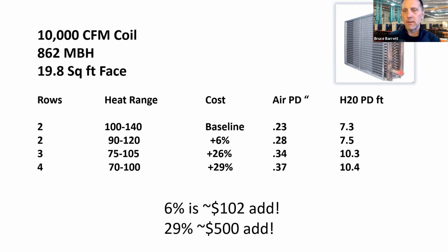And the COP benefit that you get, I'm not telling you what temperature to design your heating system, but I think it's valuable to look at that temperature and the impact across the board. It appears to be very minimal, driving towards about 120 degree hot water with your coil cost and your airside pressure drop. Again, all of these coil selections were 862 MBH. You can heat with 100 degree hot water. You just need a 4-row coil and you suffer some pressure drop loss through your coil and some fan kW.